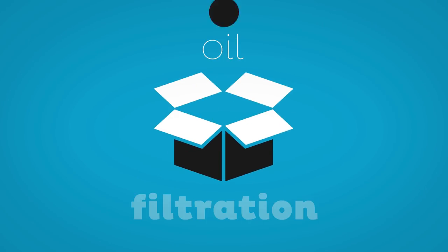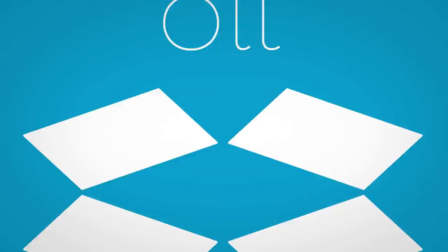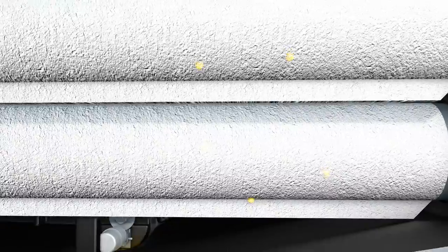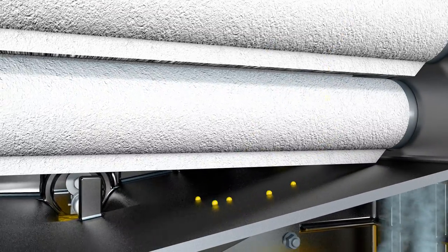The oil at the bottom of the oil box is filtered and used to inject the vacuum generator. Due to the low gas speeds, almost exclusively oil aerosol enters the exhaust filters.